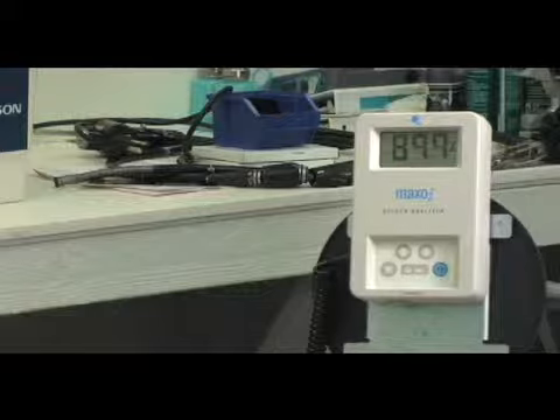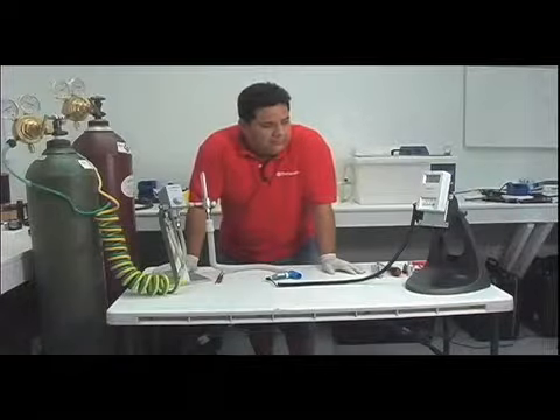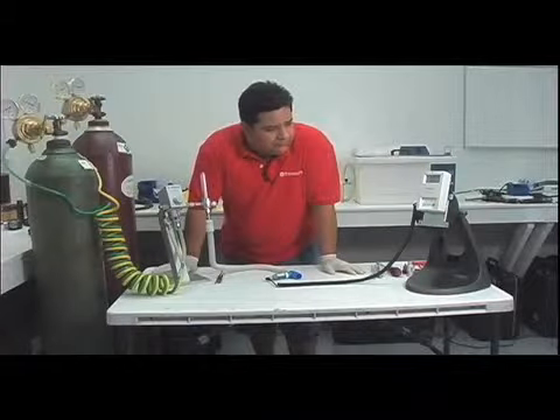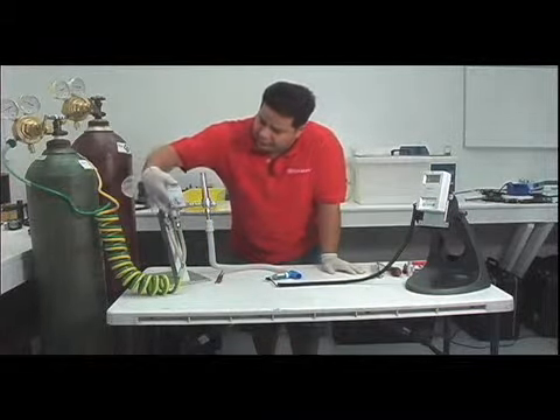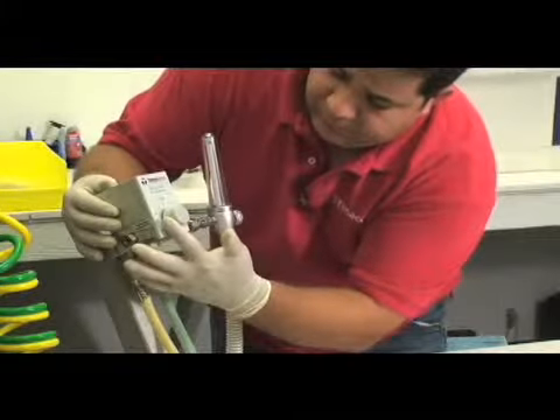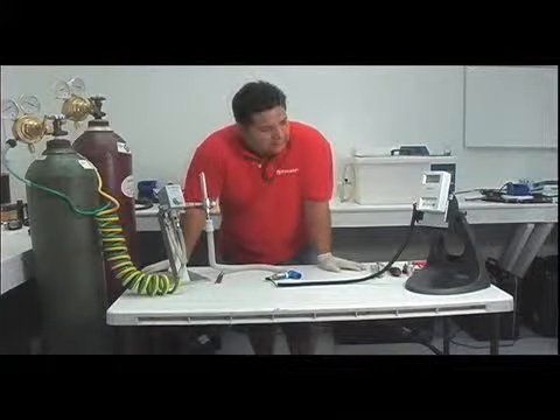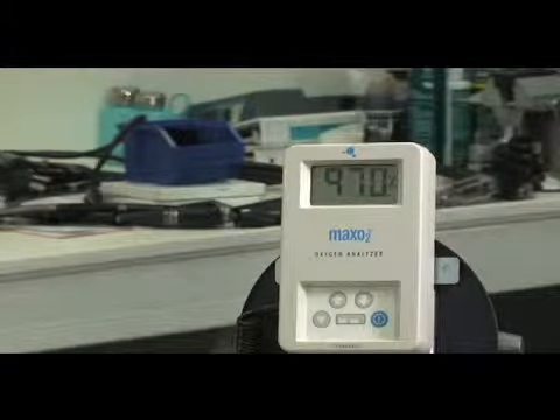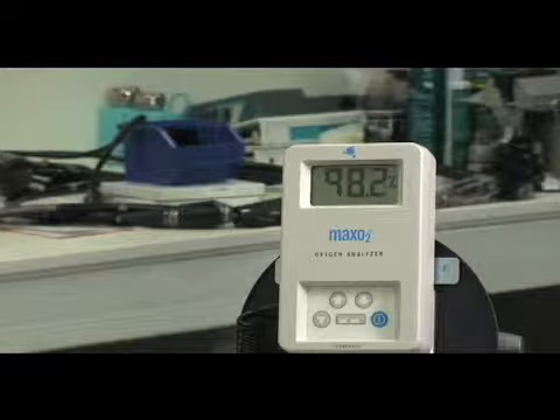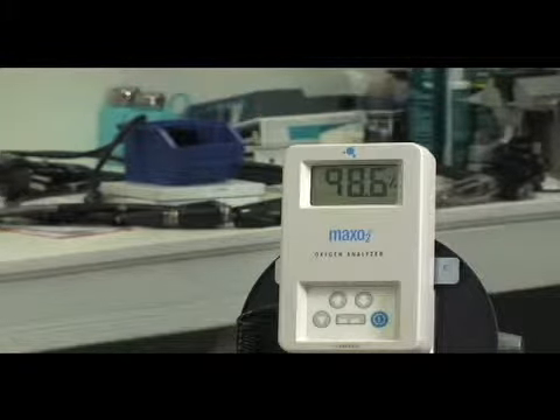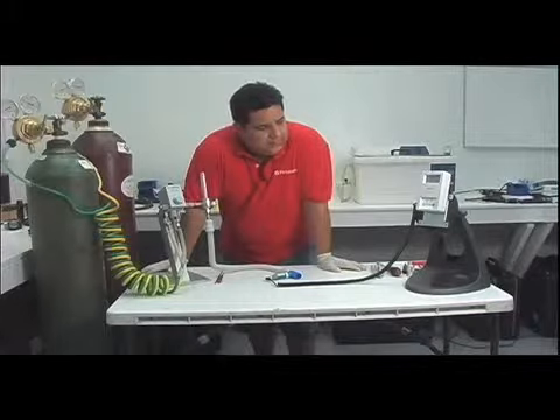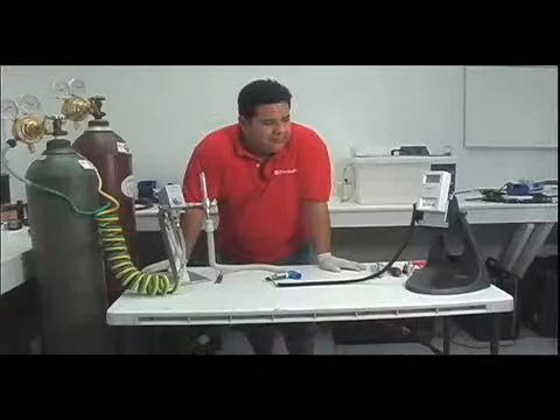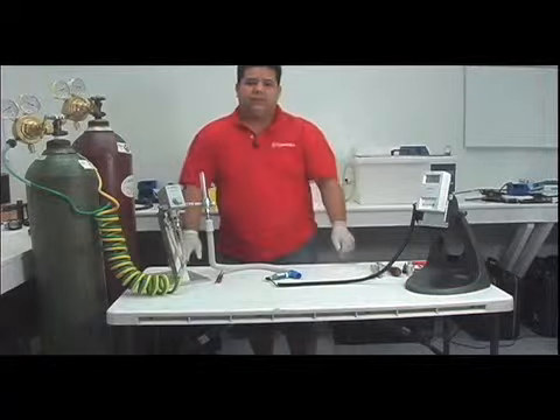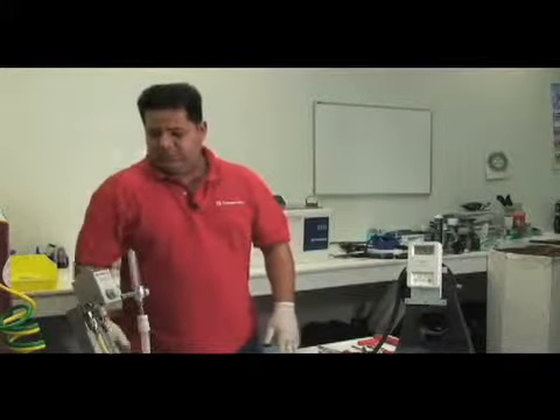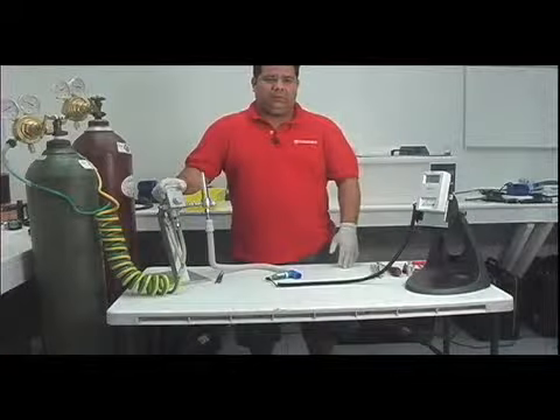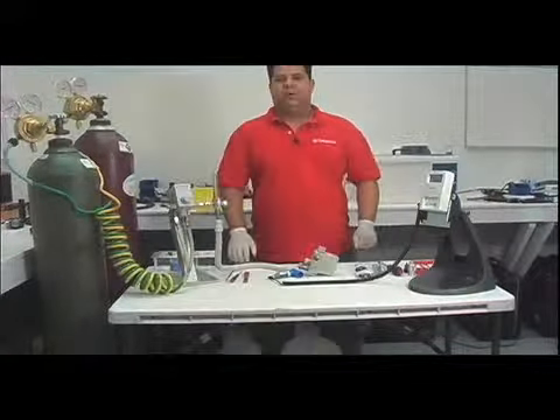90% is looking really, really good. We're right on the dot, so you can feel happy about this calibration. 90 point something. So we're going to dial to go to 100. Oxygen analyzer is moving kind of fast, which is good for us. We need to be between 97 and 103, and we're right there. So this is our last reading. We now can say that we succeeded on an oxygen blender calibration, and we can proceed to do our alarm calibration. All right, here we go.